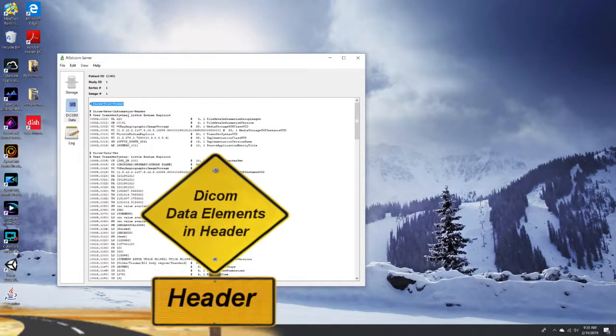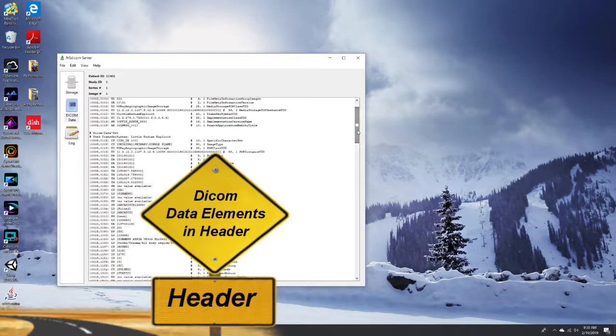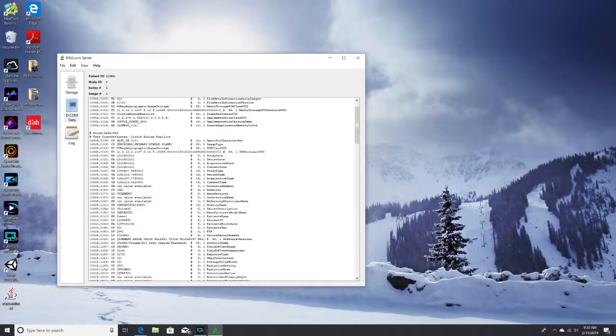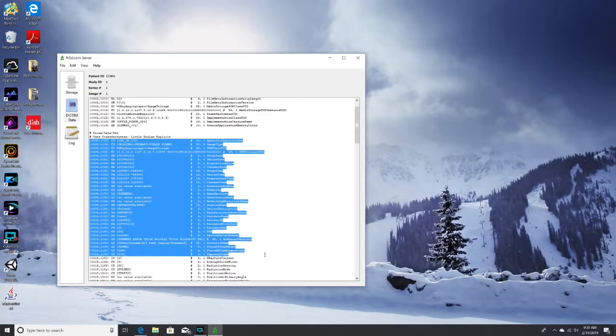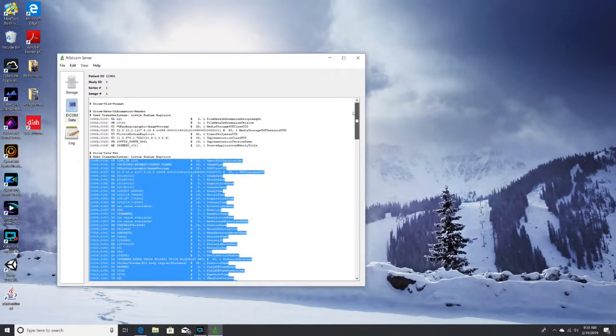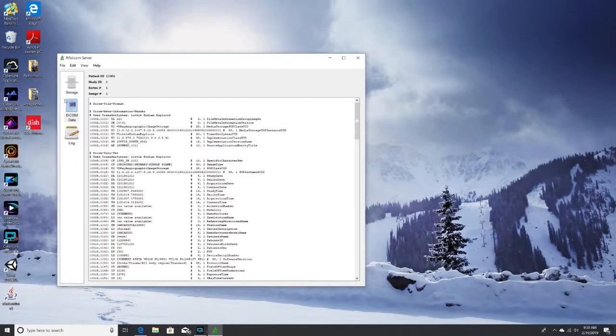This is good troubleshooting if you're having issues with the Dicom headers or something to do with the Dicom, you know, the IT is complaining or PACS is complaining. You can pull this up and show it to them and have them tell you where the problem is. But in this instance, as you see, we have sent images across. Most likely it is not on the machine side. It is either a setting that they have given you, a setting wrong on the machine, or something to do with IT or on the PACS side.